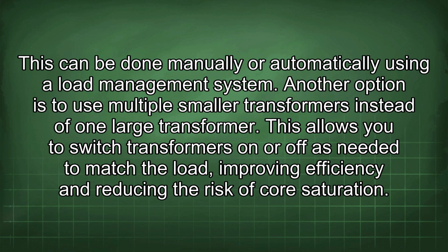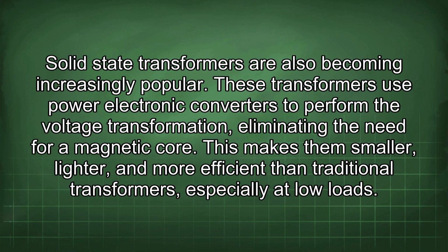Another option is to use multiple smaller transformers instead of one large transformer. This allows you to switch transformers on or off as needed to match the load, improving efficiency and reducing the risk of core saturation. Solid-state transformers are also becoming increasingly popular.